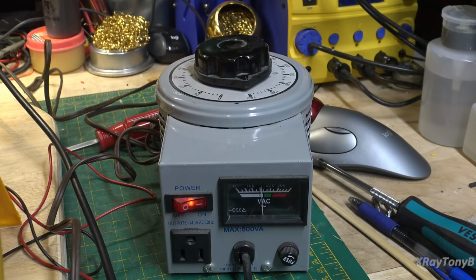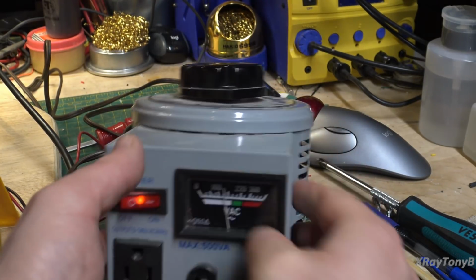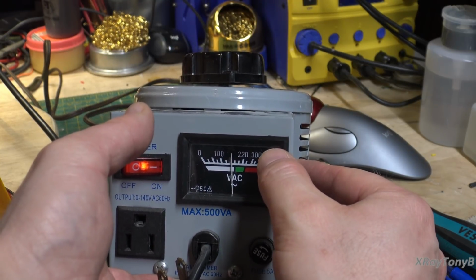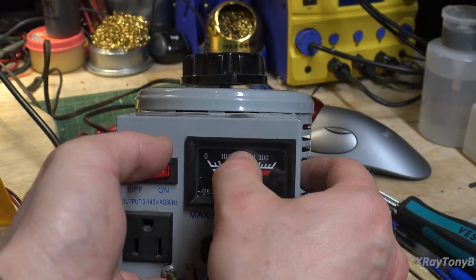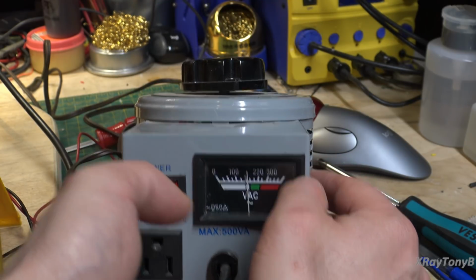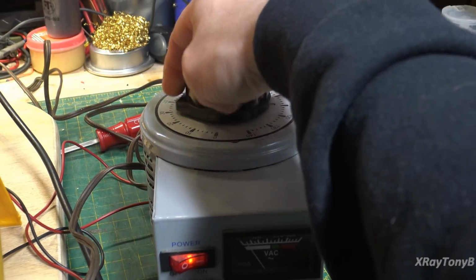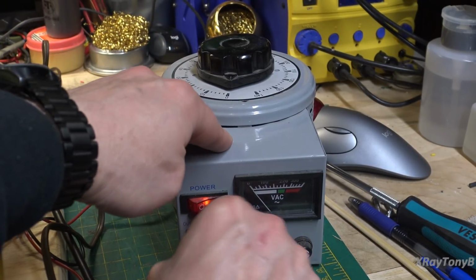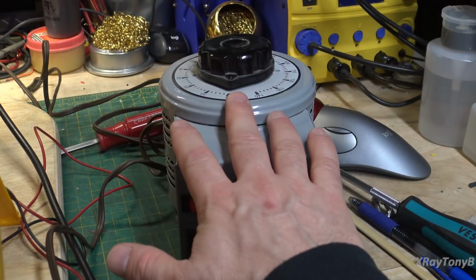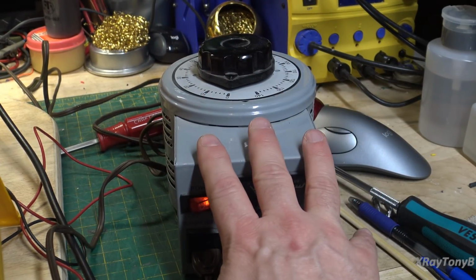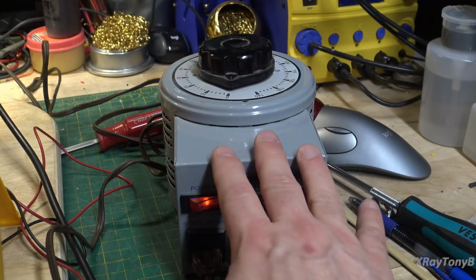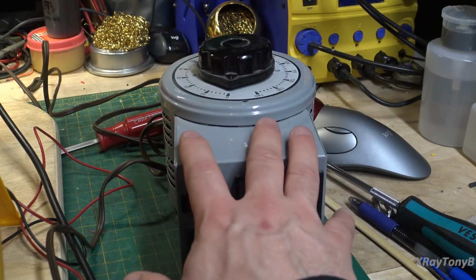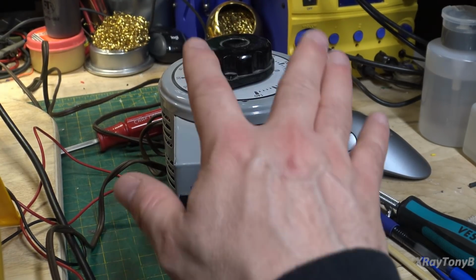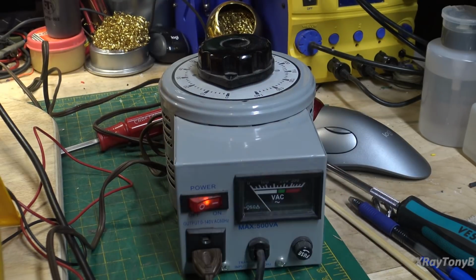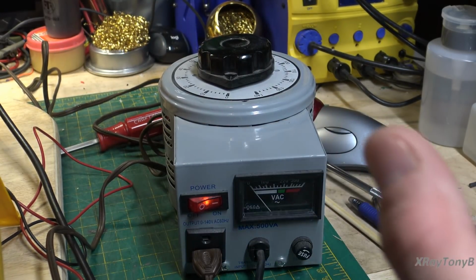And this meter actually goes up to 300 volts. So you could see 50, 100, and 150 volts. You could see it's reading right around 150 roughly. So we start at 0 volts, and you would plug your device into it. And fancier versions of this will also have an amp meter in it, so you can monitor the current, and that's extremely important. So normally I do not power anything up just like this. I will actually have an amp meter and voltmeter on this as I do it.